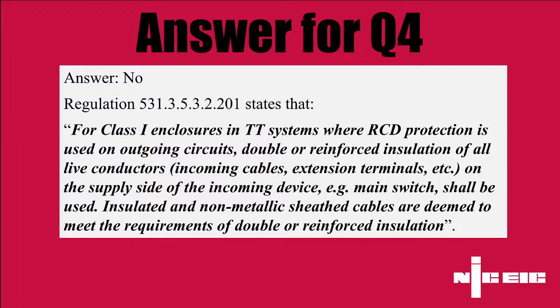That's where we go. But if you go back further, you can look at regulation 410.3.3, for example. We talked about the four protection measures, that each part of the installation should have one or more of, and indent 2 is double or reinforced insulation, which can be found further in section 412. And there we'll just cite that basic protection is provided by the basic insulation, and fault protection is provided by the supplementary insulation, or basic and fault protection is provided by the reinforced insulation between the live parts and accessible parts. So you can see the relation.